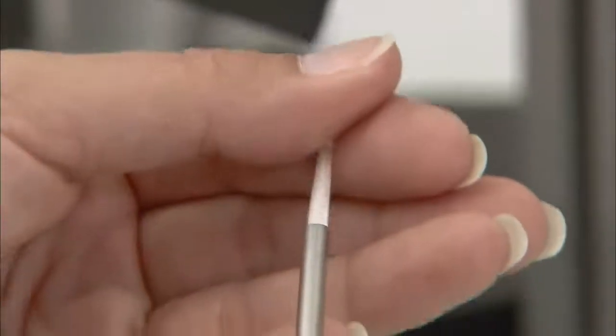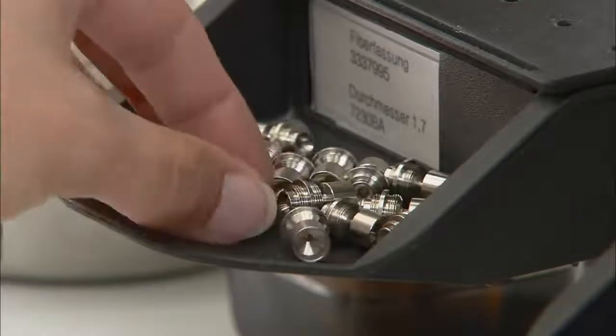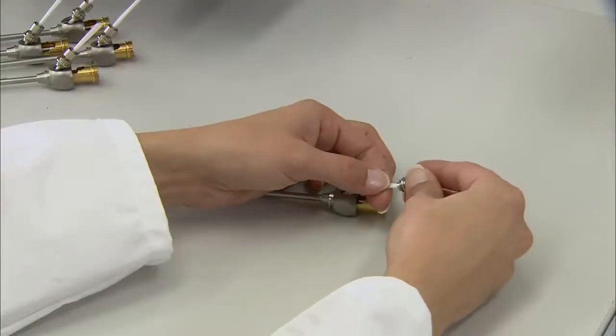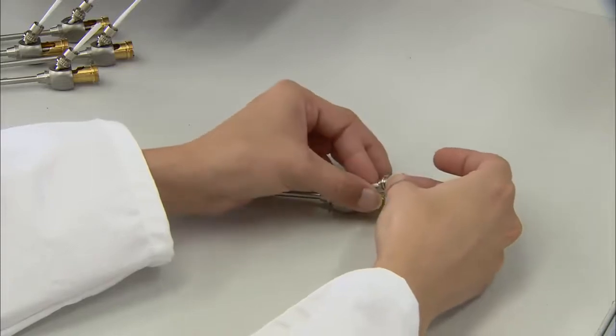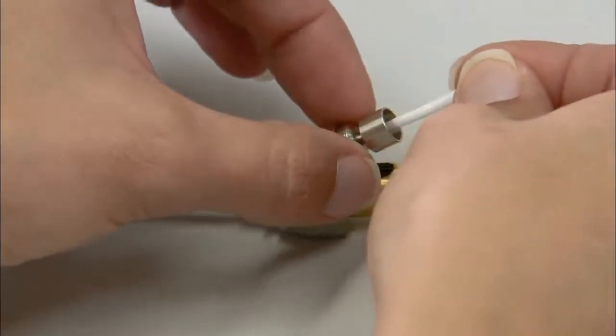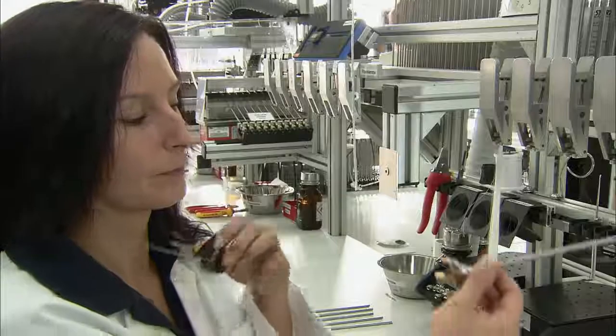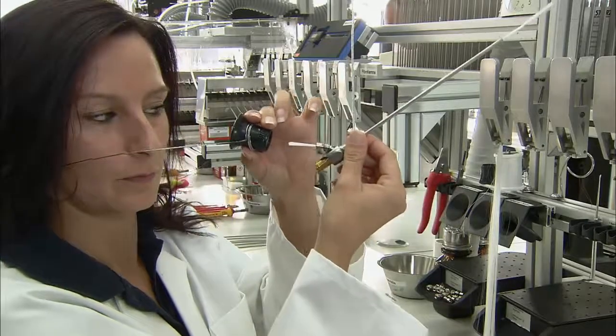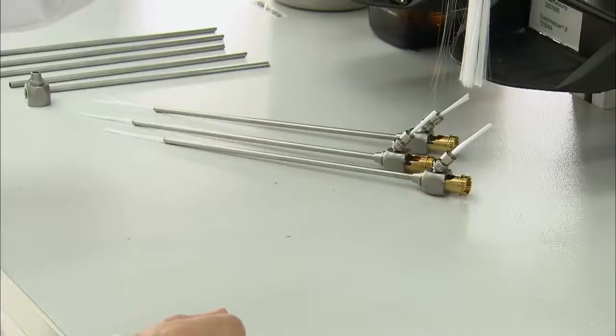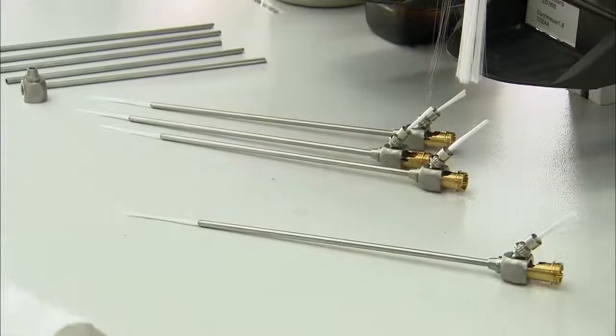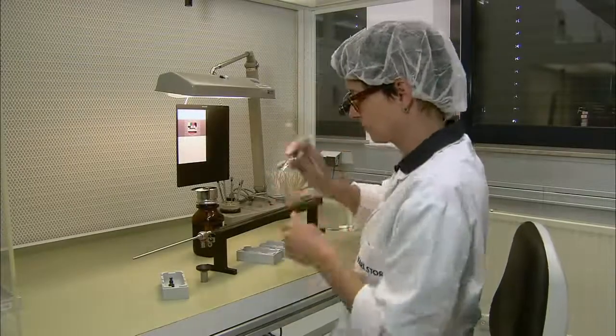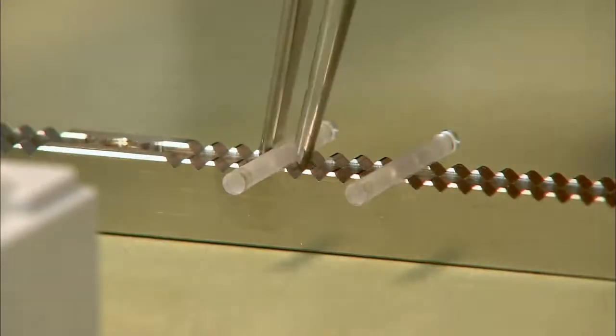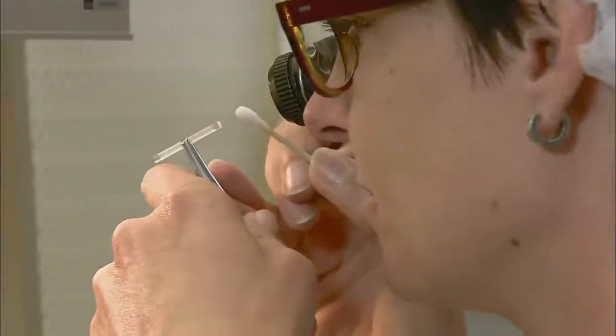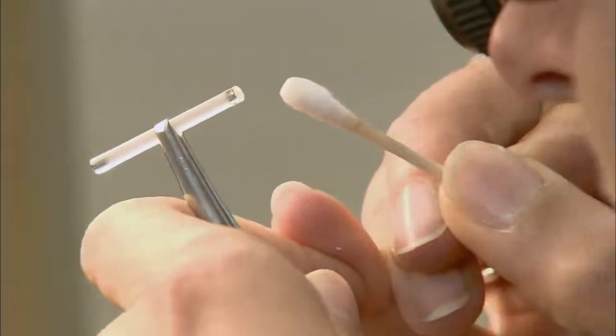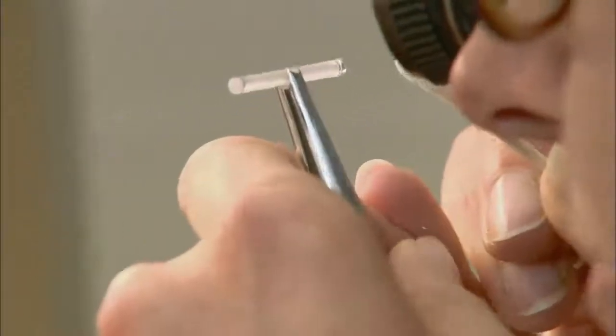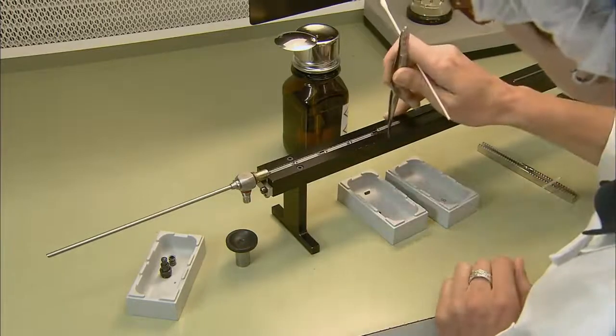A stainless steel adapter is now attached to the protruding optical fibers. This will connect the cable from the operating room light source to the endoscope, transferring light to the optical fibers inside the device. The fibers are now inspected under magnification to check for black spots. These would indicate broken fibers, which would interrupt the transmission of light. An endoscope transmits an image much like a telescope. Optical lenses send reflected light, which produces the image from inside the patient, all the way to the surgeon's eye, peering through the top. The endoscope's lenses are made from glass rods.